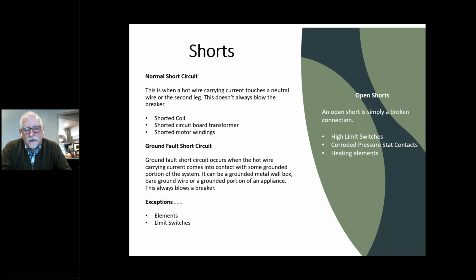I'll use ohms to check transformers on circuit boards. I'll use ohms, of course, for elements. I'll even use ohms on probes, water probes, because I know that I should expect 600 or 700 ohms on the probe when it's passing through water. And if I'm not, that means that it could be calcified, or I've got a calcified boiler, or I don't have any water in the boiler at all.